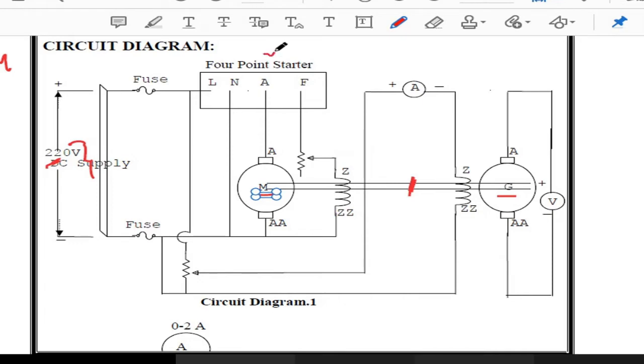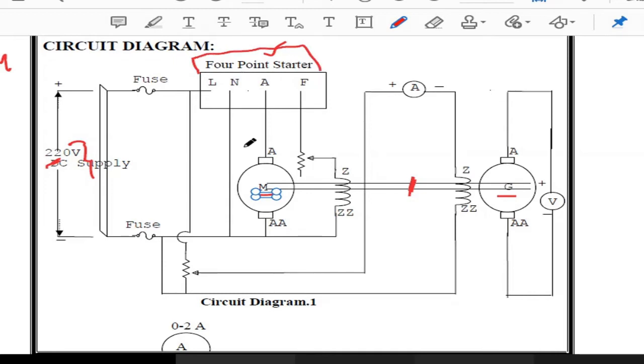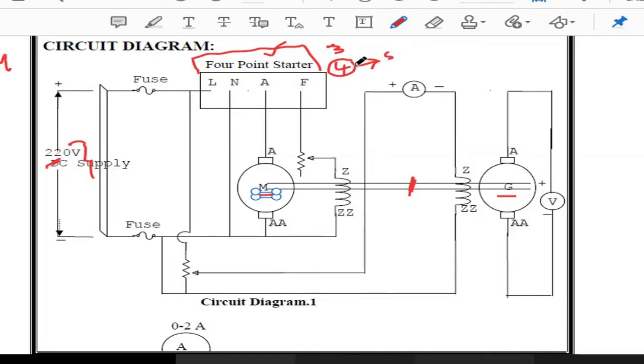The purpose of the starter is not simply to start the motor — it is mainly used to limit the starting current. By using the switch we can start the motor, but the key role of the starter is to control and limit the starting current. We have two types of starters: a three-point starter and a four-point starter. Generally, for motor experiments requiring security and high speeds, we use a four-point starter. The terminals of the starter are: Line, Neutral, Armature, and Field.